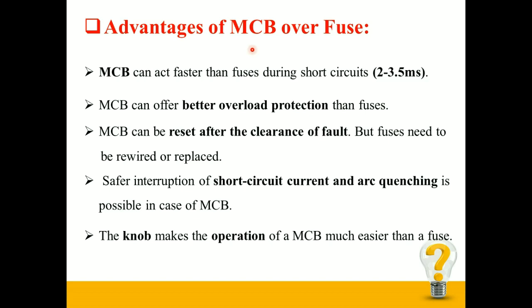The advantages of MCB over conventional fuse: MCB can act faster than fuses during short circuit conditions — as fast as 2 to 3.5 milliseconds. MCB can offer better overload protection than fuses. MCB can be reset after clearance of fault, but fuses need to be rewired or replaced. Safer interruption of short circuit current and arc quenching is possible with MCB. The knob also makes operation much easier than a fuse.